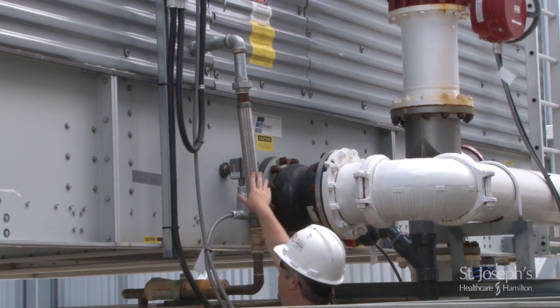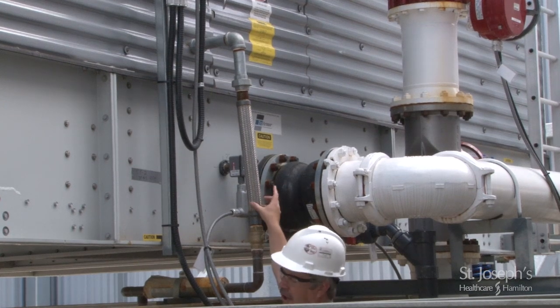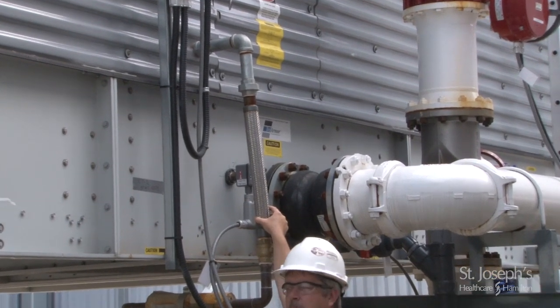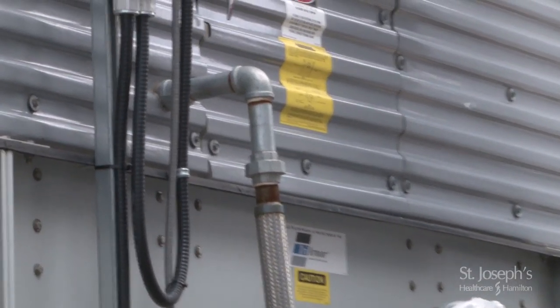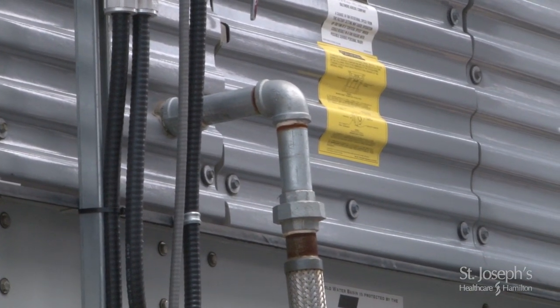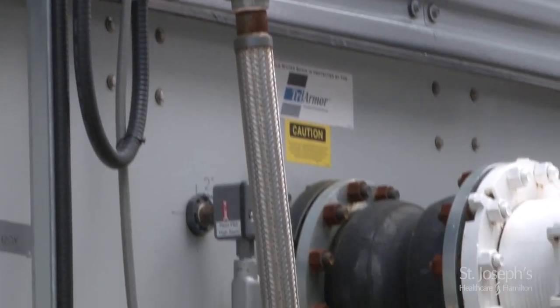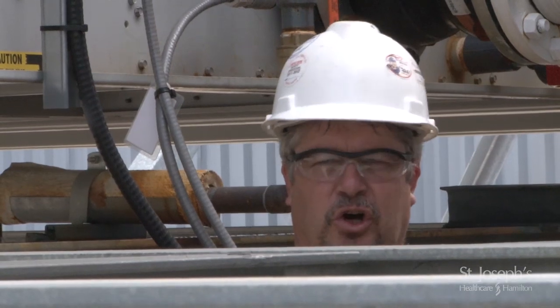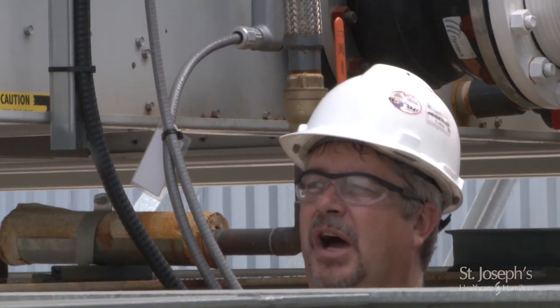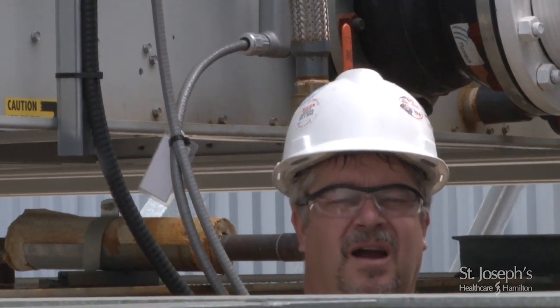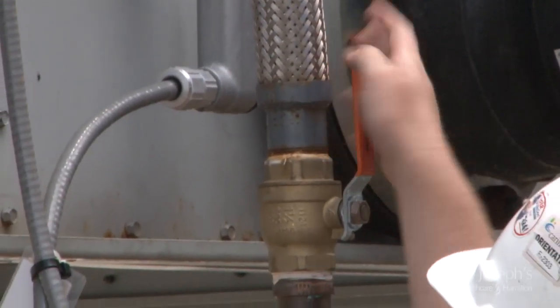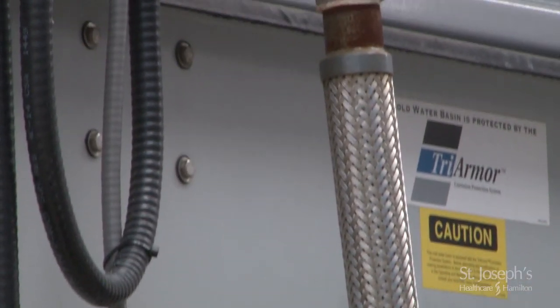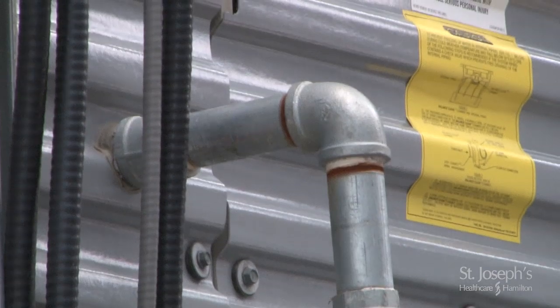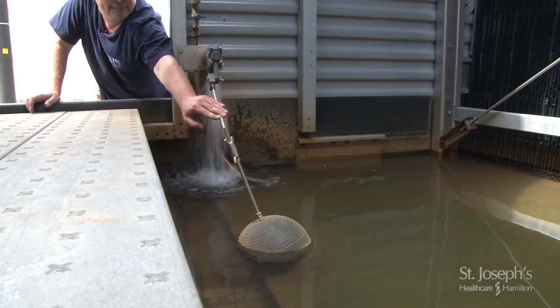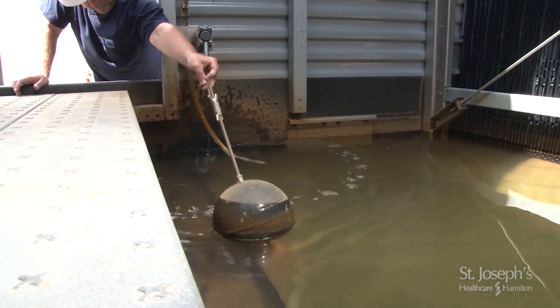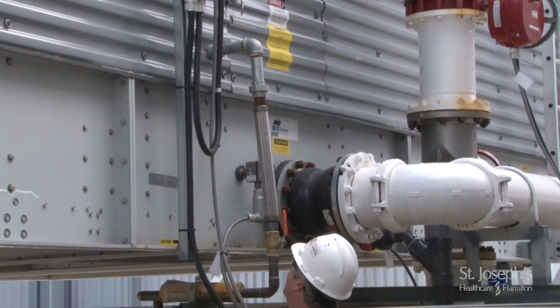This line here, coming from below the tower, is your freshwater makeup line. Basically, as the cooling tower operates, we're pumping warm water to the tower, returning cool water back to the building. Just that process alone causes evaporation, and there will be loss of water within the tower. To maintain a proper operating level, we have a makeup valve that works internally. As the water level drops, it starts to make up water till we're back up to correct operating levels, and then it'll shut off. Next to this, we have a high alarm.